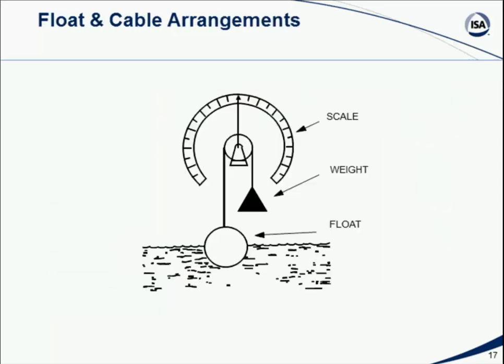Now, another type of method for measuring level that's quite often been used is the use of a float and cable arrangement. Now, this diagram is not exactly how it is ever built, but it gives you the principles. The notion in a cable float arrangement is that somewhere up in the top of a tank, above the highest fluid level, we have a pulley. And over that pulley, we suspend a float and a weight. And the float should be slightly heavier than the weight, but designed such that, for example, in this drawing, it's hollow. So even though the float is heavier than the weight, when the float drops down and hits the surface of the liquid in the tank, the buoyancy of the float counteracts its weight, and it goes no further into the fluid. And so it sits there floating on top of the fluid.